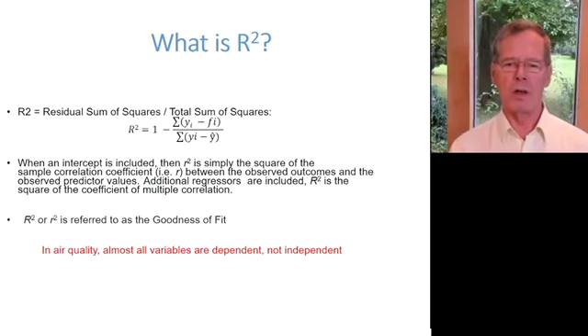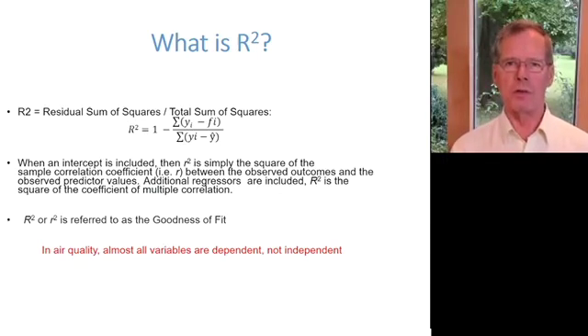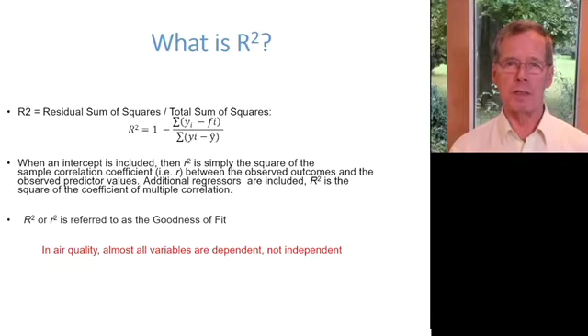Almost all variables in air quality are interdependent. For example, relative humidity will affect both your sensor being tested as well as your reference system.